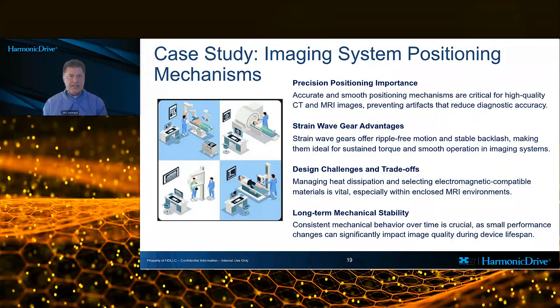So imaging systems such as CT and MRI scanners rely on precise, smooth positioning mechanisms to ensure high-quality images. Motion irregularities, vibration, or acoustic noise can introduce artifacts that compromise diagnostic accuracy. These systems often require long periods of static holding torque, placing sustained thermal and mechanical loads on the actuators. Strain wave gears are well suited to this application due to their smooth, ripple-free motion and stable backlash characteristics. Integrated actuators simplify installation and alignment in large gantry systems, reducing assembly risk. Design trade-offs include managing heat dissipation in enclosed spaces and selecting materials compatible with electromagnetic environments, particularly in MRI systems.